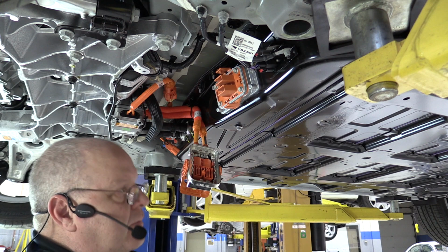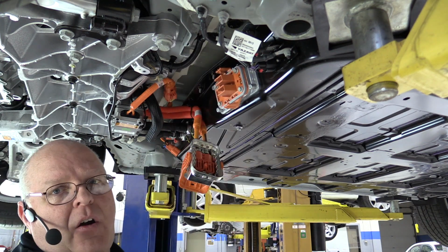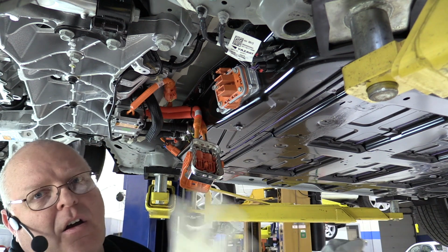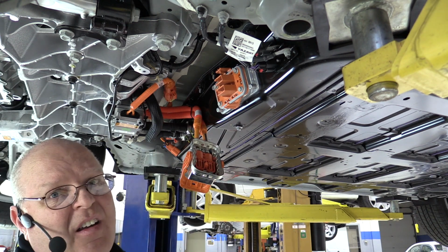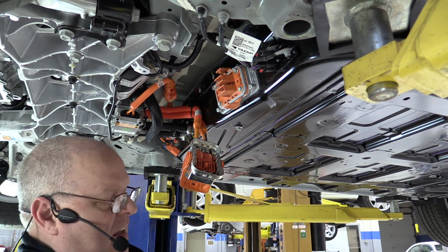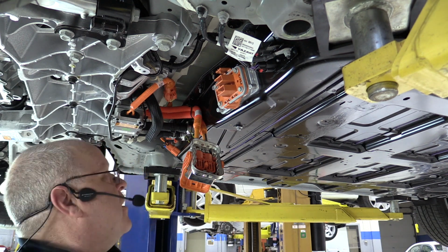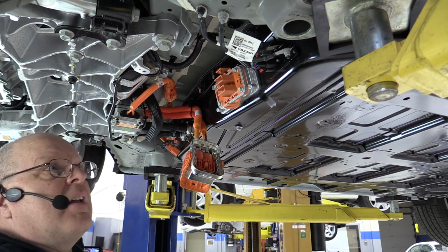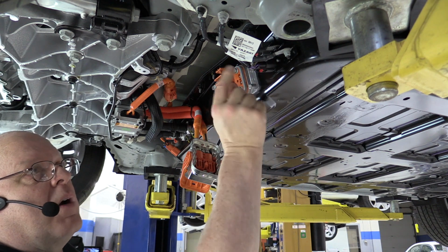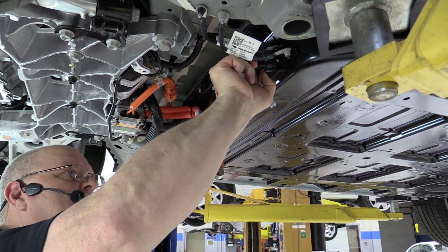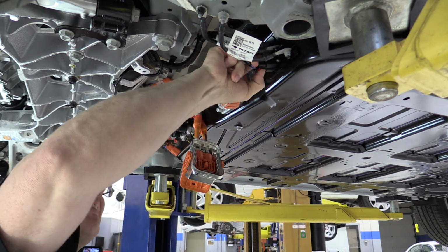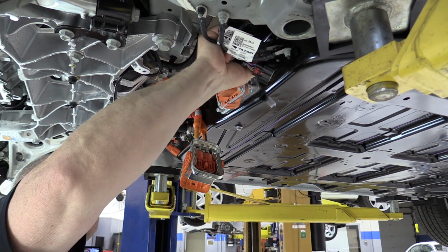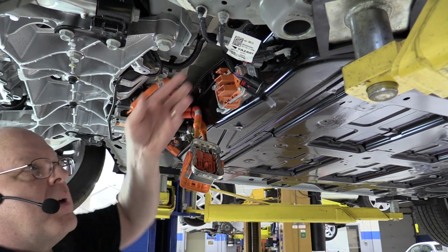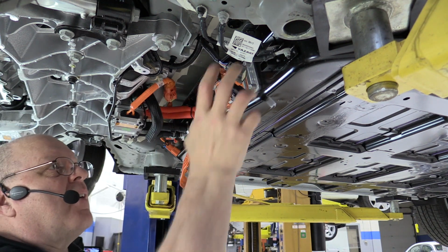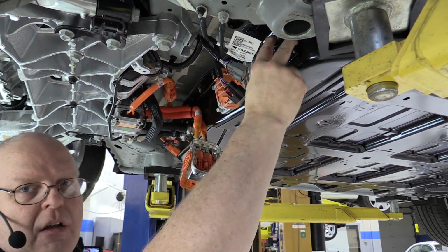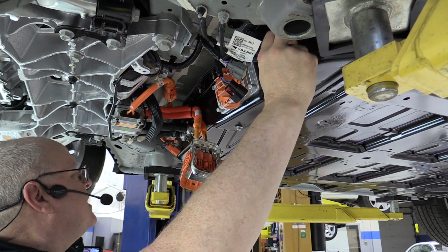So at this point, we have no high voltage anywhere here, and I'm going to take off my high voltage gloves because they get hot, they're awkward to work with, and if you don't need them on, you don't need them on. All right, so the next steps are to disconnect the 2 electrical connectors here. We've got 2 low voltage connectors. Each one has a red terminal position assurance clip and a little pin that we compress and take out. We have two bonding ground straps here that we need to disconnect.